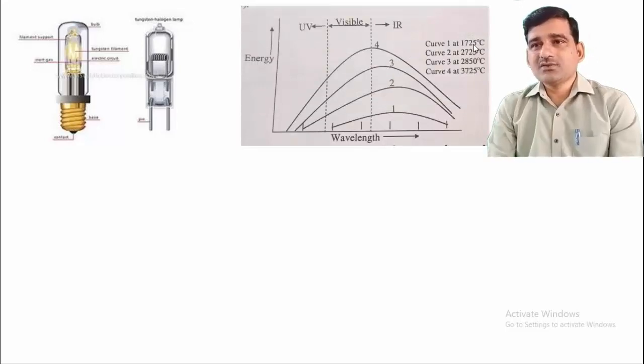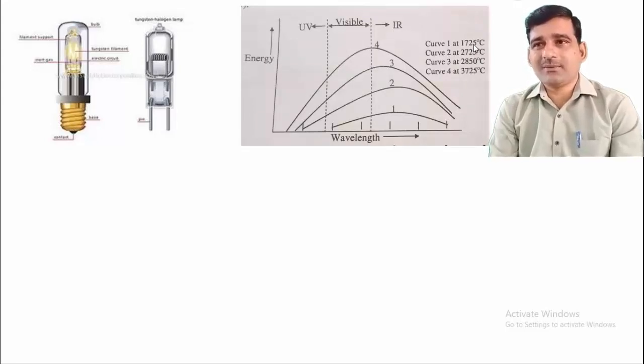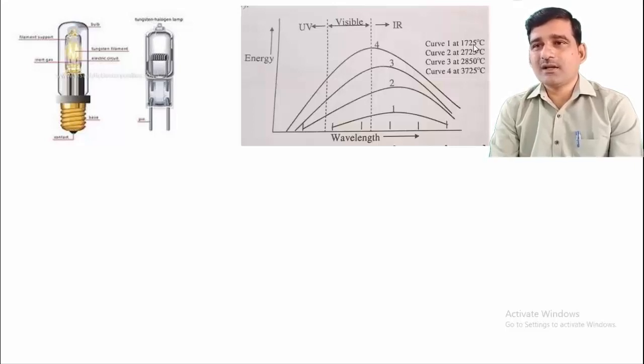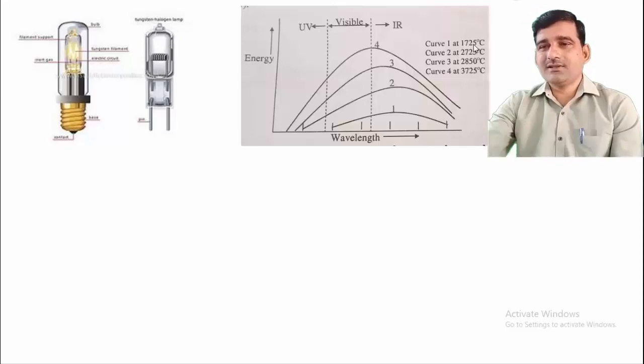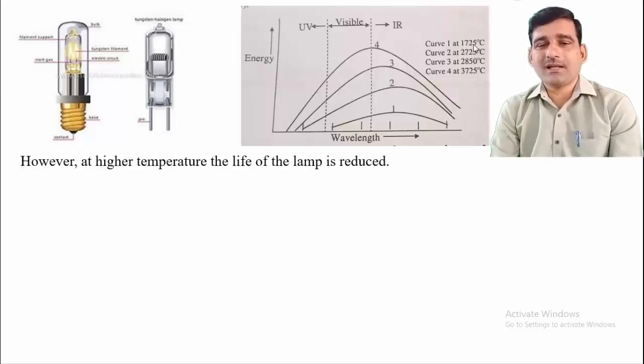A graphical representation shows the operating temperature versus emitted light in the UV, visible, and IR regions. At 1725°C (curve 1), more radiation is in the IR region. As temperature increases to 2725°C (curve 2), more radiation appears in the visible region. At 3725°C, the lamp gives more intense light in both UV and visible regions — but at higher temperatures, the life of the lamp is reduced. Therefore, it is desirable to use a moderate operating temperature that balances visible-region output with lamp life.